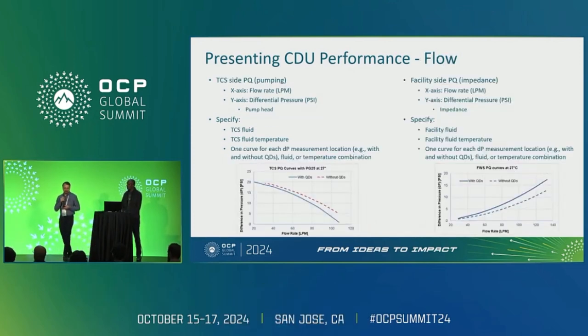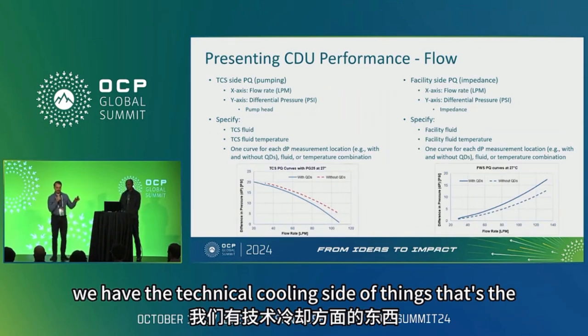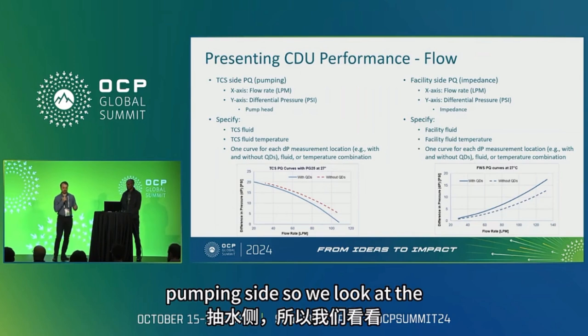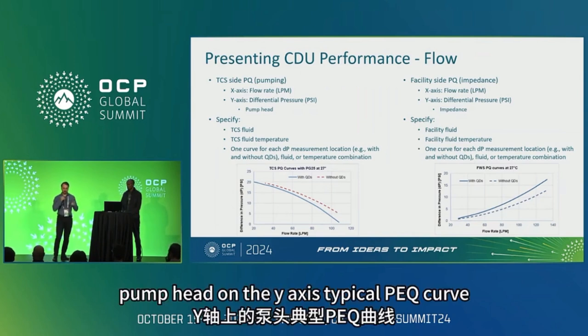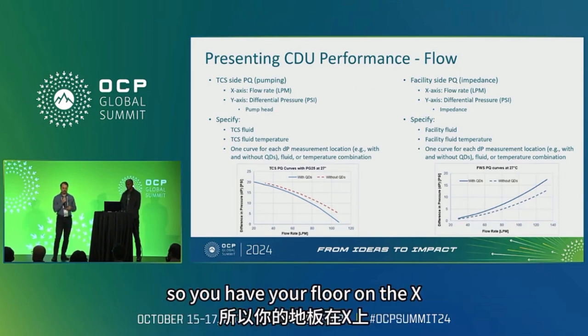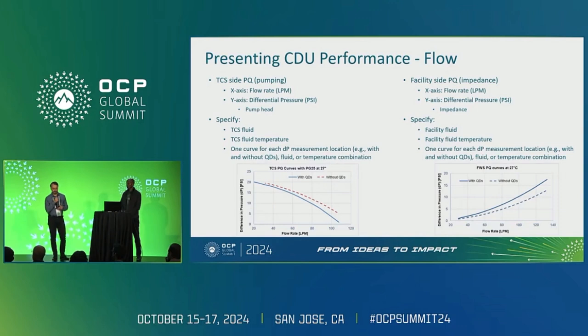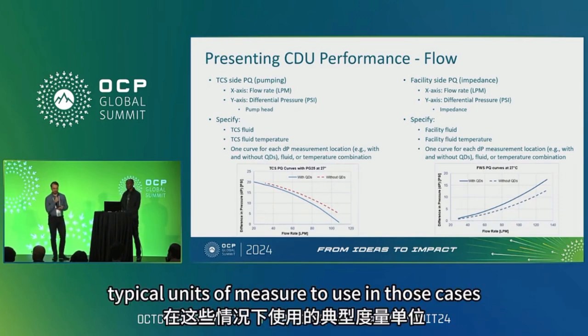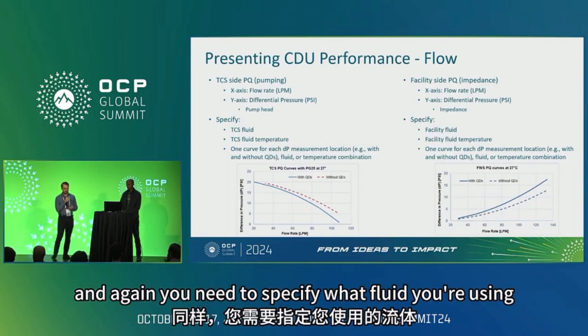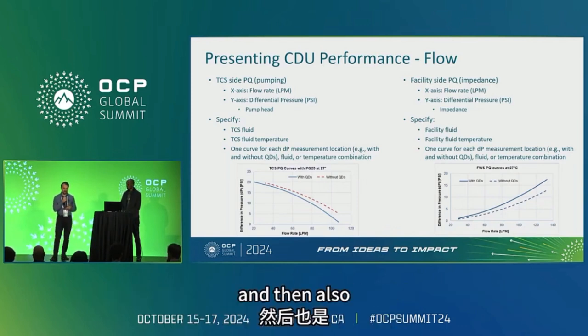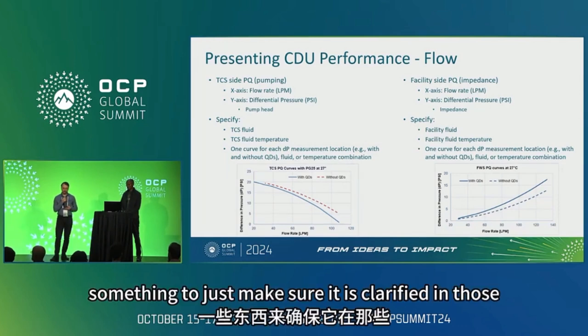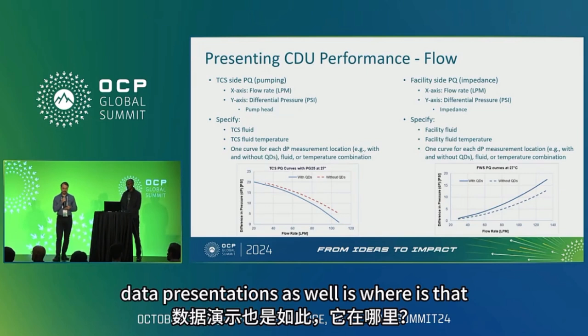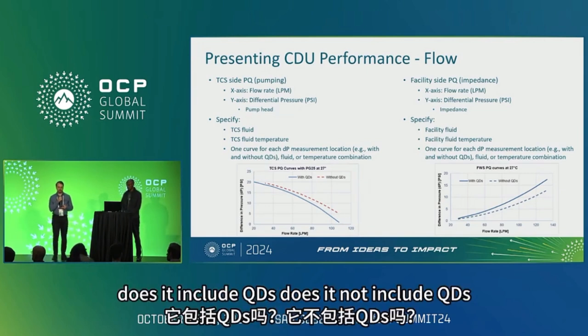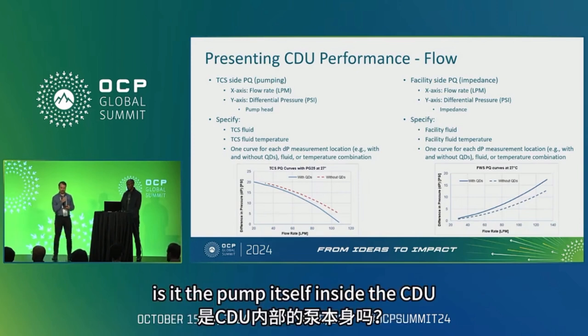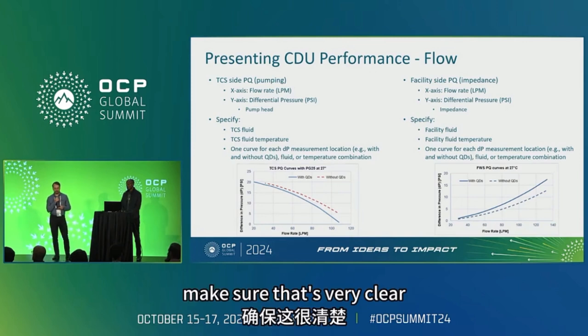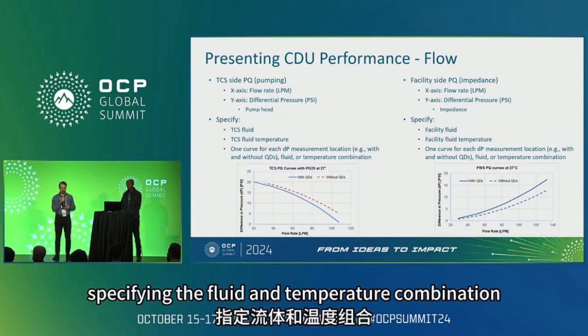On the flow side, we have the technical cooling side of things. That's the pumping side. So we look at the kind of pump head on the y-axis, typical kind of PQ curve, but in this case it is a pressure head curve. So you have your flow rate on the x, pump head on the y. We propose some kind of typical units of measure to use in those cases. And again, you need to specify what fluid you're using, what temperature it's at, and then also something to just make sure is clarified in those data presentations as well is where is that DP being measured? Does it include QDs? Does it not include QDs? Is it the pump itself inside the CDU? We'll make sure that's very clear. And then specifying the fluid and temperature combination.